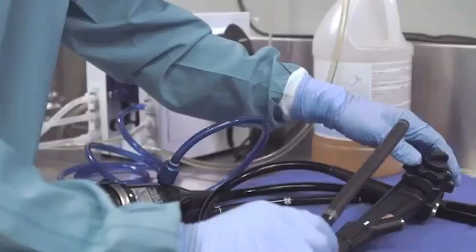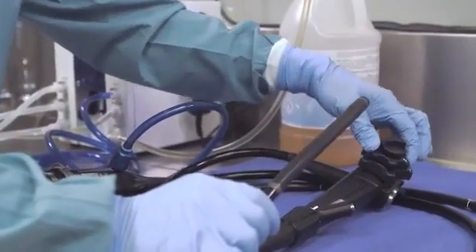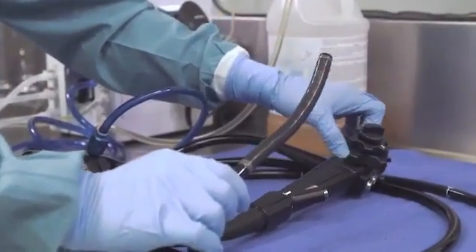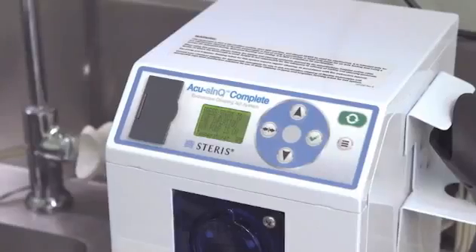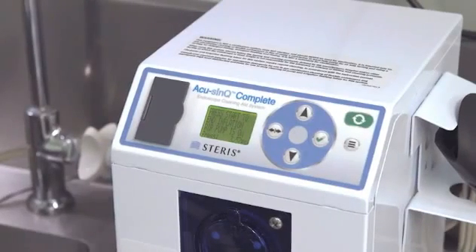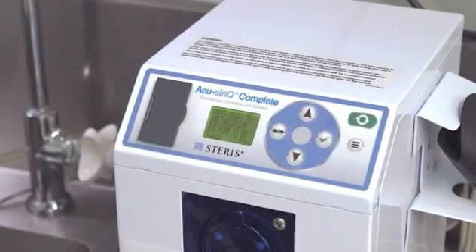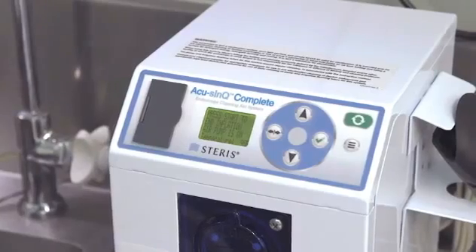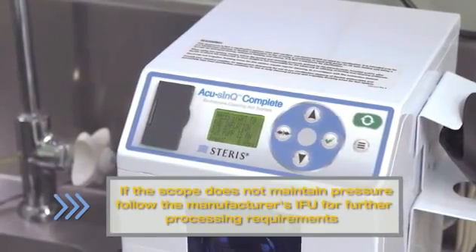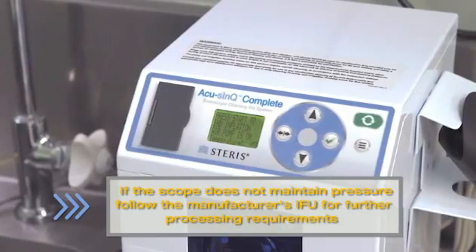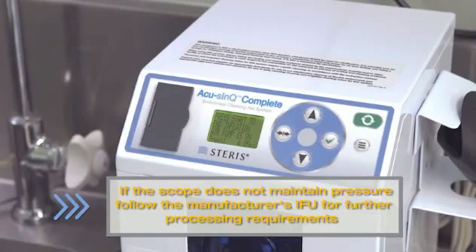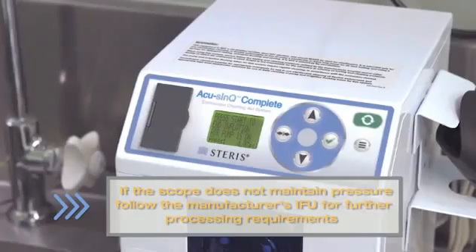Watch for expansion of the rubber sheath and manipulate the control knobs in all directions. If the scope maintains pressure for 30 seconds, the display will remain green. If the scope does not maintain pressure, a red screen will appear. If the scope does not maintain pressure, follow the scope manufacturer's IFU for further processing requirements.